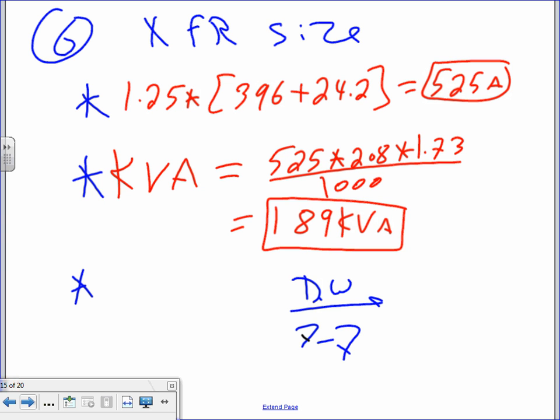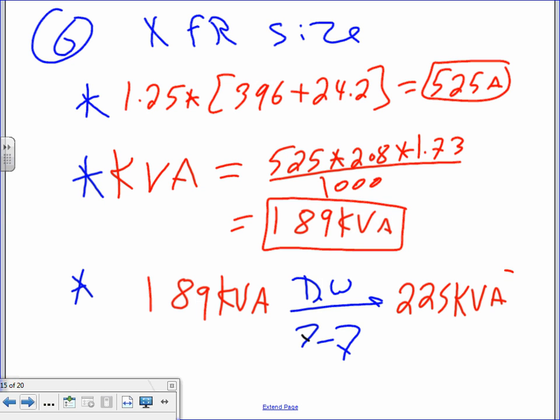There's one little problem. 189 kVA does not exist. They don't exist. So you need to find yourself a standard kVA. Where do you go to find a standard? 7-7, that will get you 225 kVA. 225 kVA. That would be the size of your transformer.